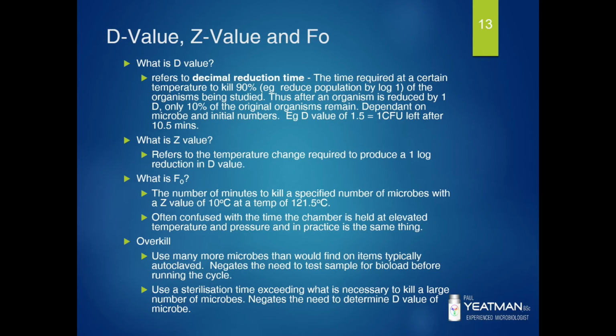Well, we use many more microbes than we would find in items typically autoclaved, which negates the need to test the sample for bioload before running the cycle. So we have these millions of microbes on a spore strip, whereas the routinely autoclaved equipment might have, say, 1,000, maybe 10,000. Like, really worst case situation. Using a sterilisation time exceeding what is necessary to kill a large number of microbes negates the need to determine the D value of the microbe. And also for a decon cycle, if you validated 20 minutes for your normal routine loading pattern, putting media in there or dirty equipment and autoclaving it for 60 minutes should be a long enough time to kill everything off.